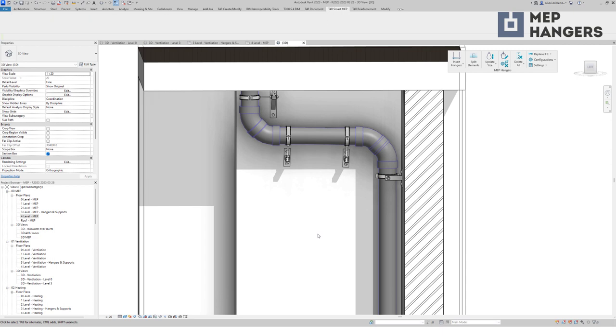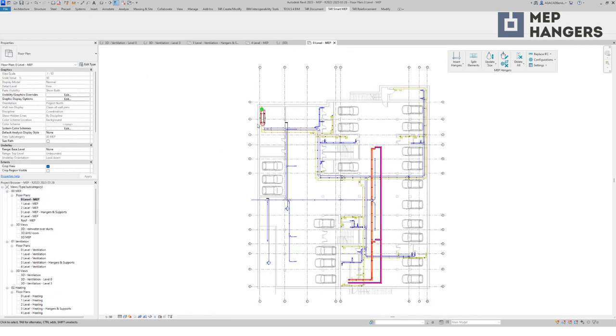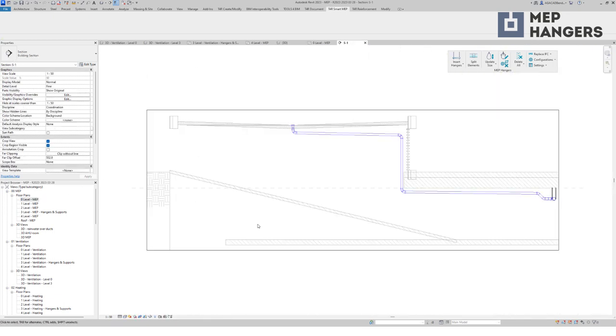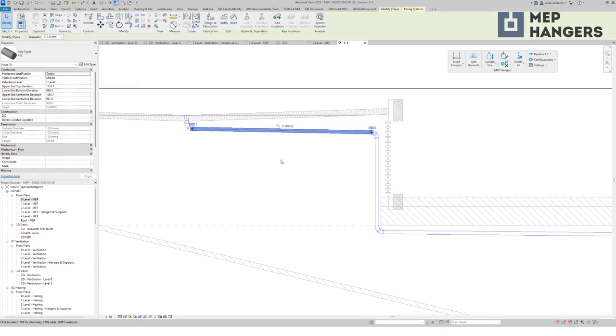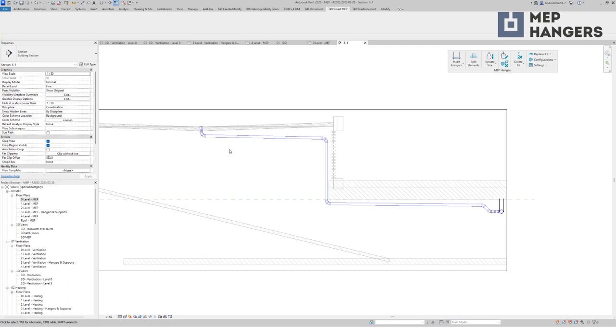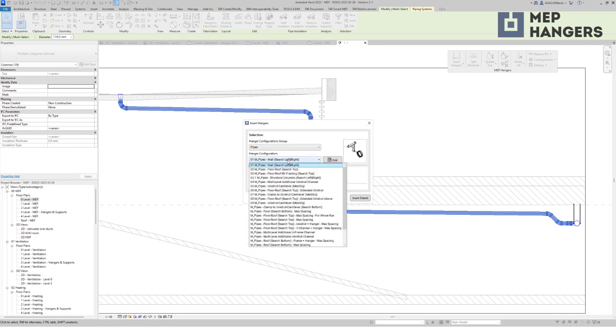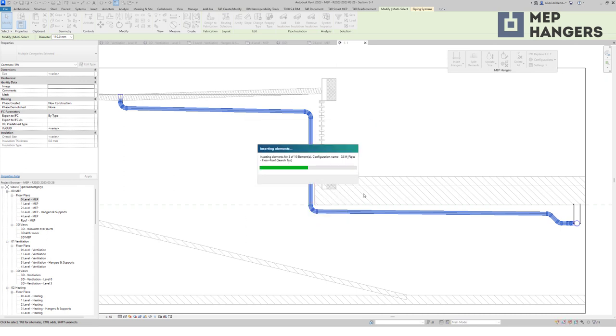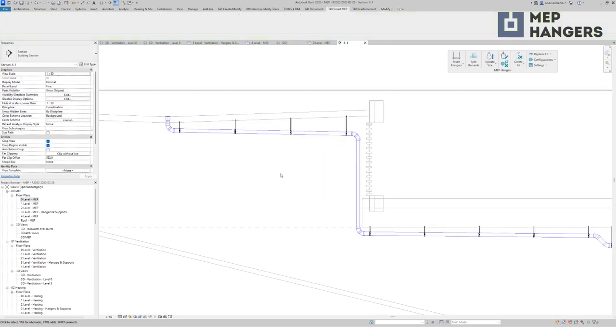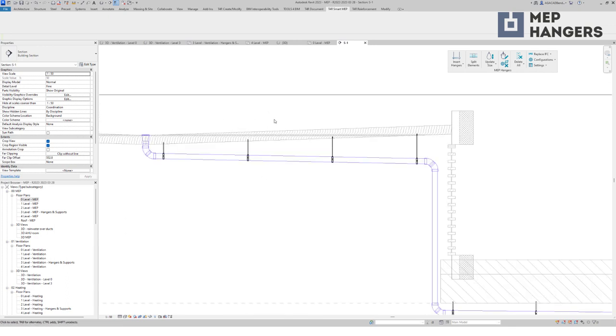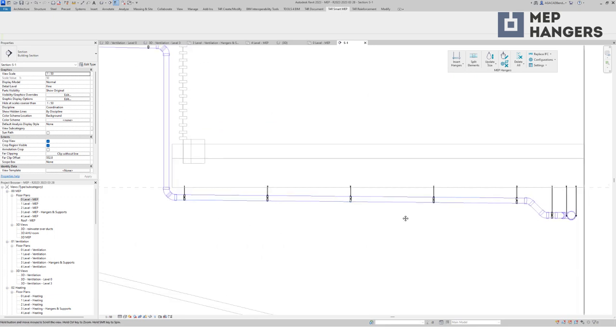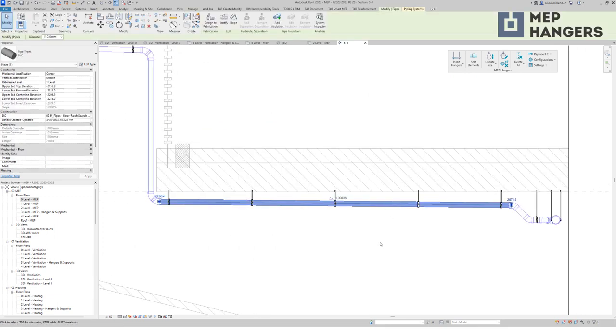Now let's take a look at some sloped pipes. I will find them in my underground level. MEP Hangers can handle sloped pipes, sloped surfaces, or even both at once. Selecting pipes, choosing a configuration, and the result is this. Notice that I have different rod lengths for my hangers here — that's because our software calculates the needed rod length for every point on a pipe. And the flat deck is also no problem.